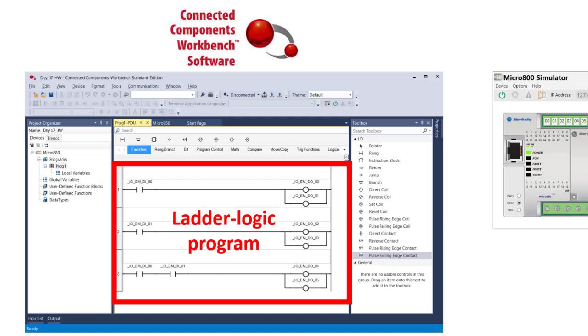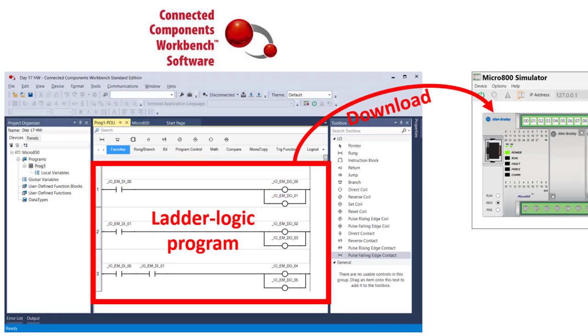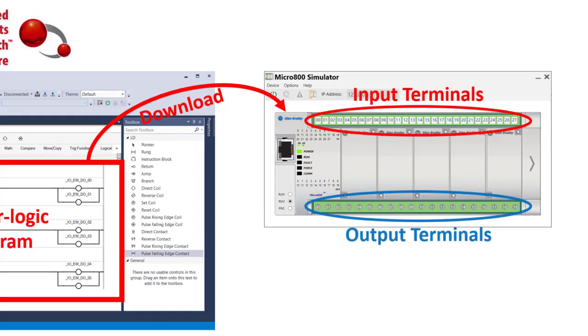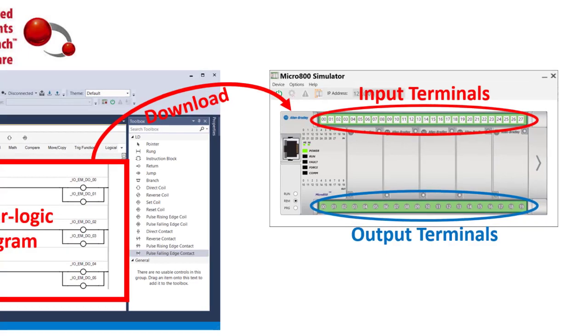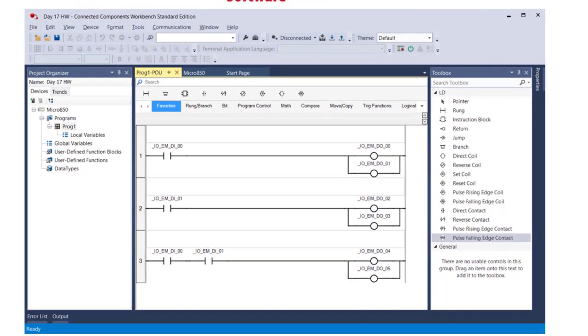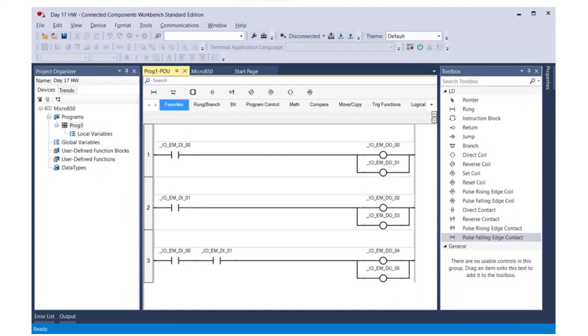Here's an example of a very simple ladder logic program which you will be creating in this assignment. Once the program has been written, you download it to the PLC, which can then run it. A PLC consists of input terminals, where wires from various switches and sensors are connected, and output terminals, where wires are connected to the various devices to be controlled. A PLC program is simply the logic that reads input signals and determines what the resulting output signals should be. The ladder logic programming language allows you to write a program in a visual way, similar to how you would create a wiring diagram using relay contacts and coils.